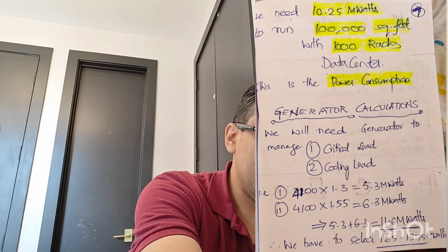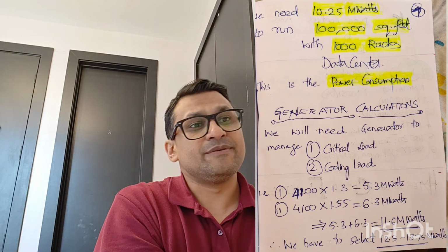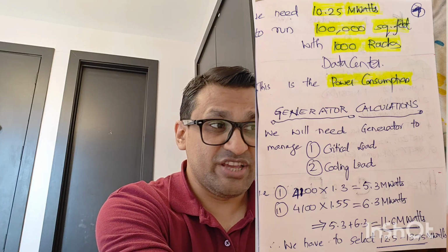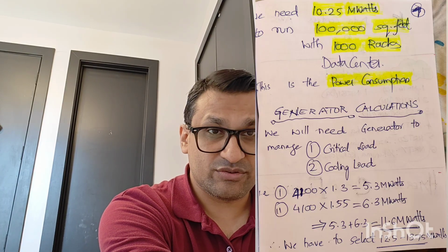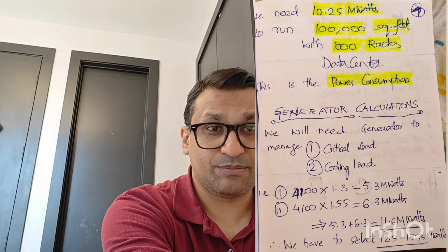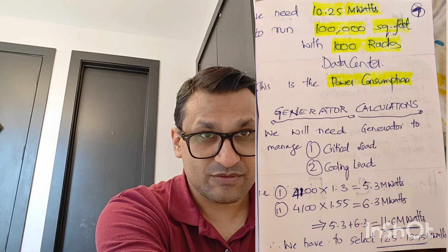So you are adding 25% extra, and we need 10.25 megawatt to run a 100,000 square feet data center with 1,000 racks. This is the power consumption. So that's the power requirement for 100,000 square feet. So that's a basic design.